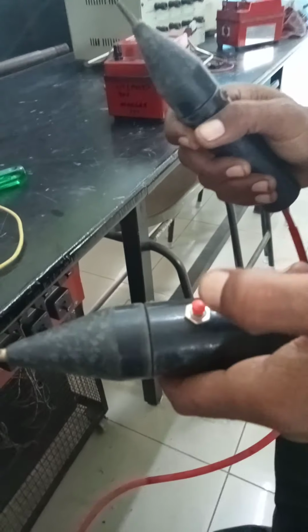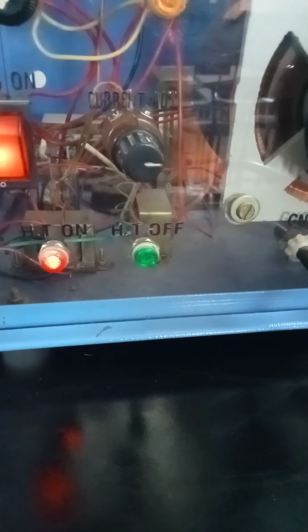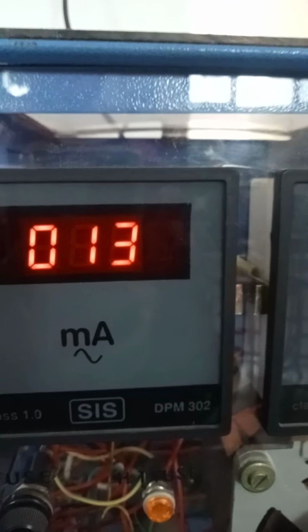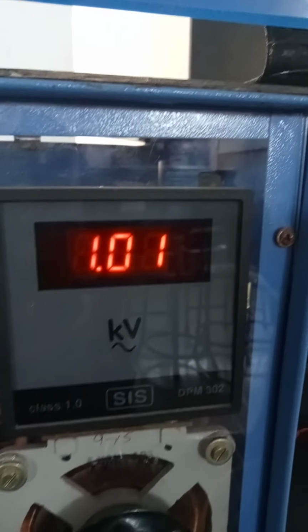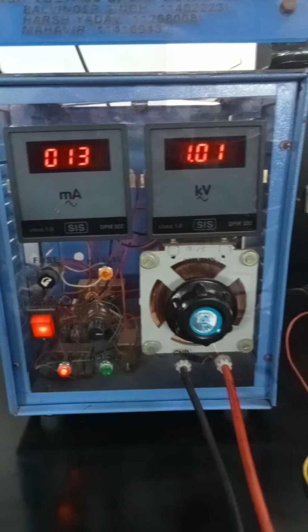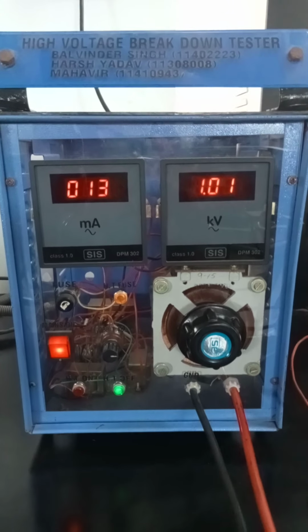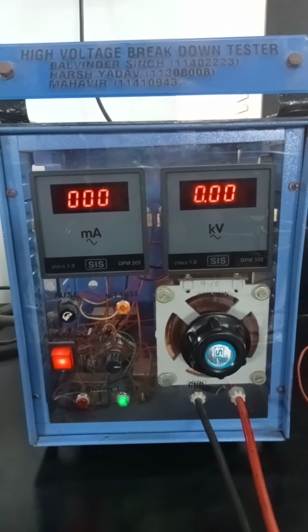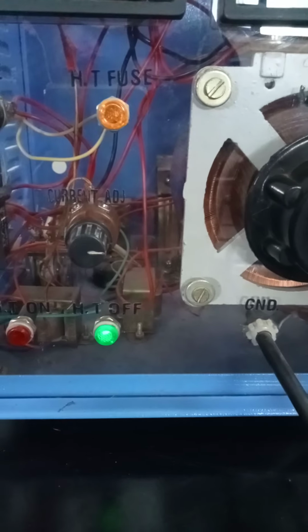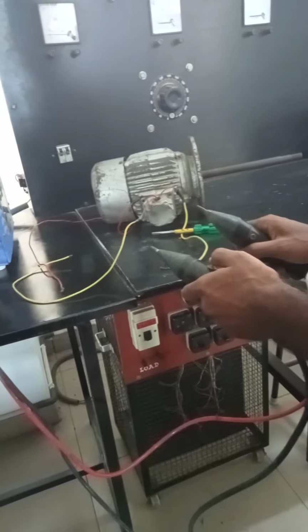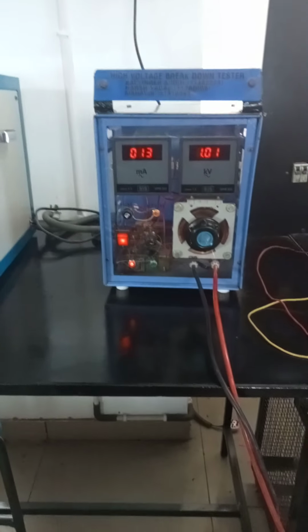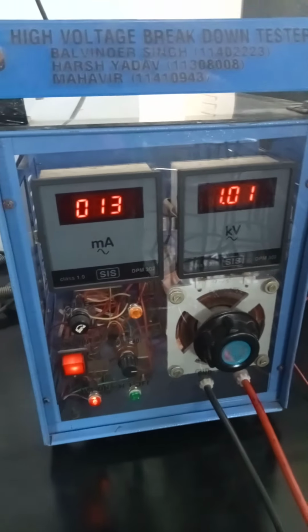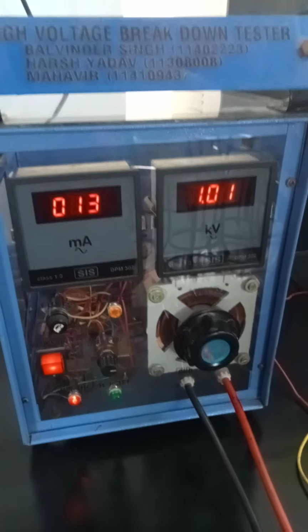Now when we operate this switch, see, again high tension supply is on. Look at the value. Again the value of current is same, voltage is same as we have set. So in the fault condition, the moment the fault comes, all the values are reset. Sir, kariyo ek bari short. See, the moment it is short, all the values become 0 and you can see HT off, green light is on. Now we will reset it. Sir, kariyo plus. The moment we have reset it, all the values are same. So this is how we are going to perform high voltage test across a 3-phase induction motor to check its insulation resistance.